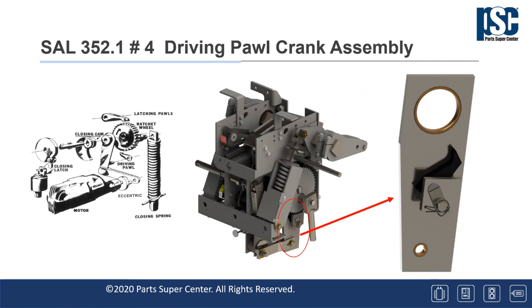Next is number 4, also on Service Advisory 352.1, which revised the driving pawl pivot pin assembly to improve reliability. The previous design had a pin welded to the backer plate. Operating experience over the years showed that the weld on this pin was not as reliable as intended. The revised design eliminates this failure mode. This change was introduced into production on circuit breakers manufactured in 1979 and later. This advisory is recommended to be added during the next breaker overhaul.